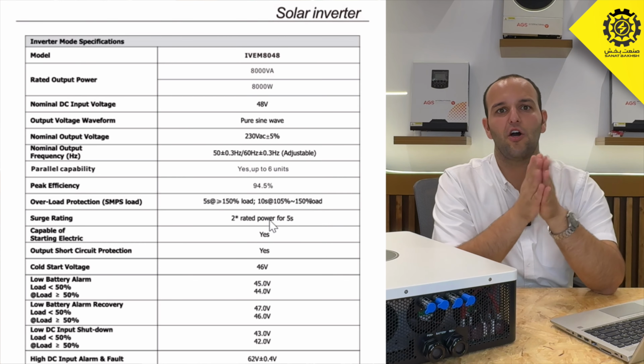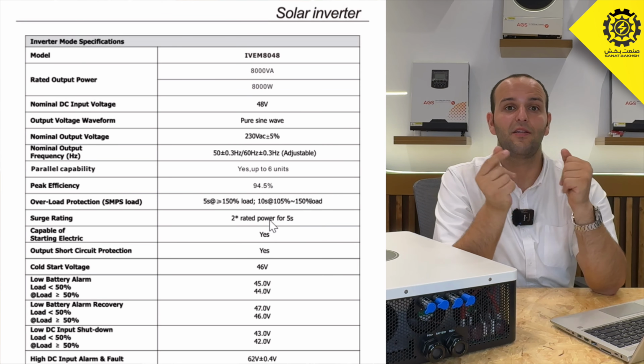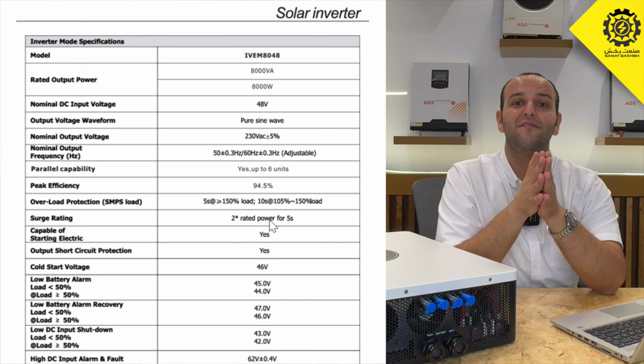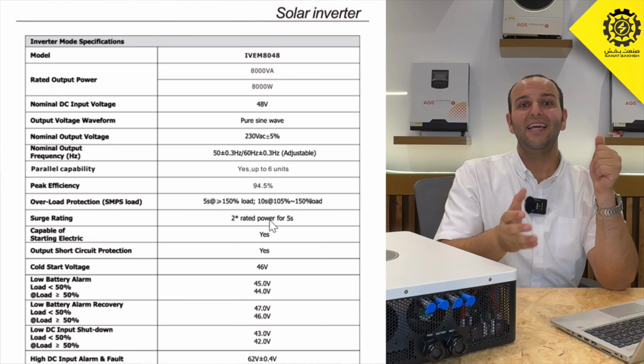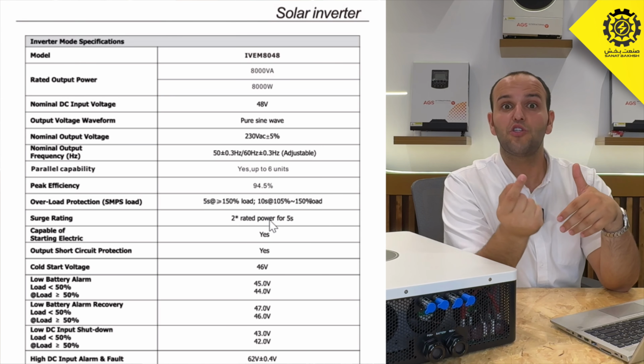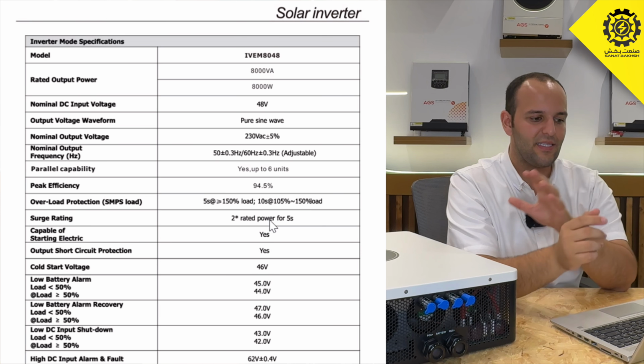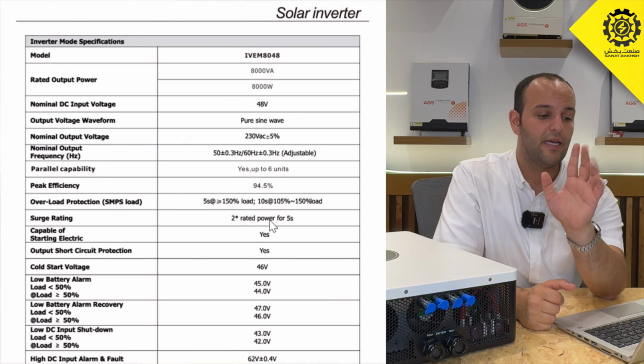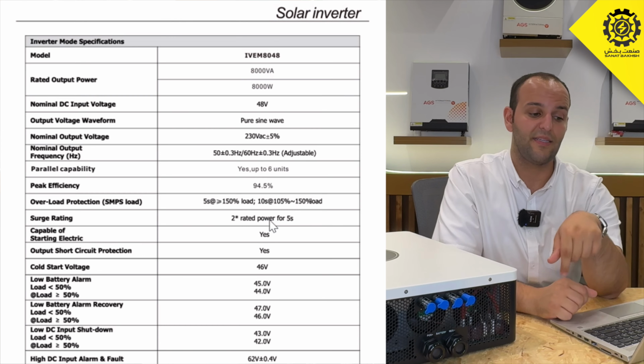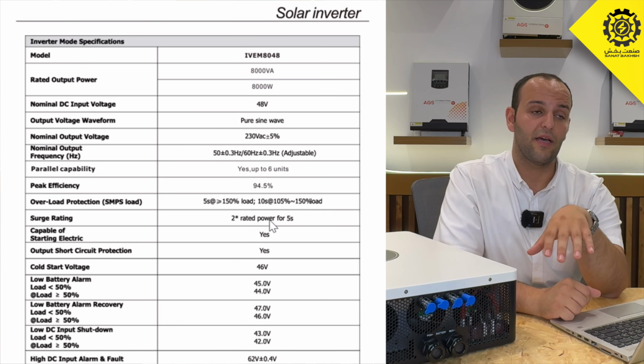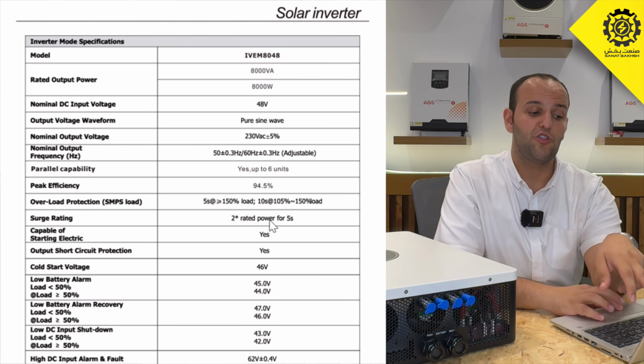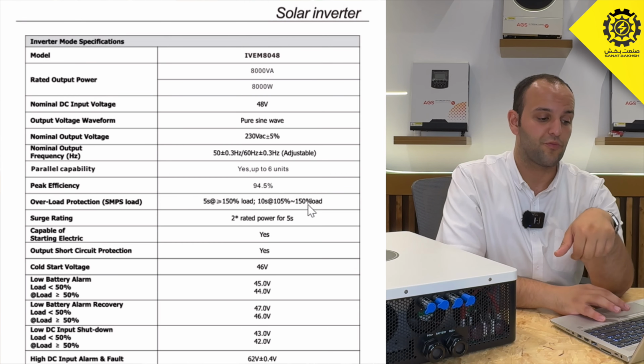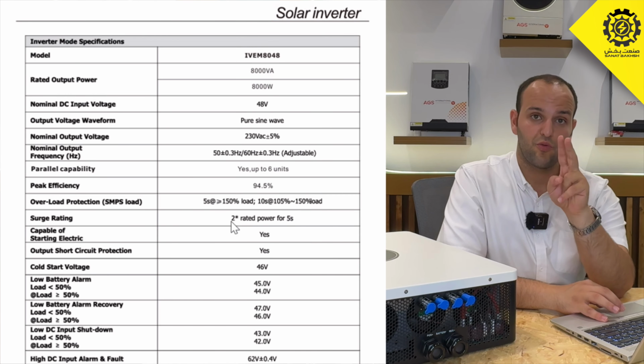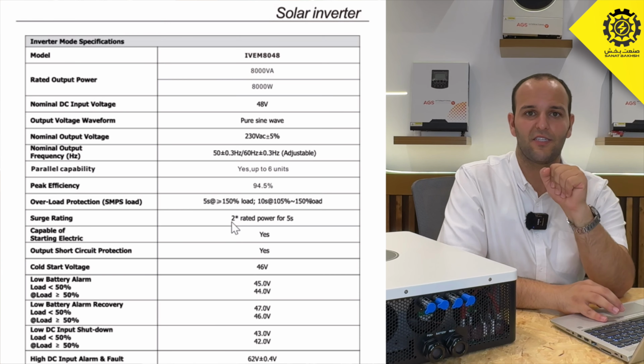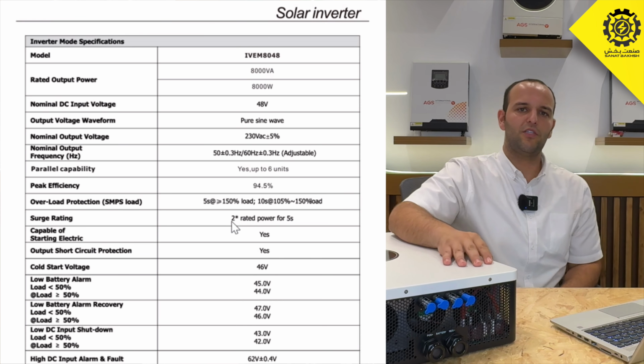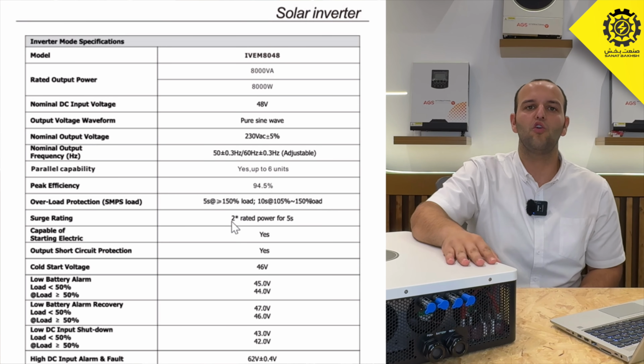For example, if you turn on your water pump, say 1 horsepower. 1 horsepower is 750 watts. At the start, it needs around 1200 watts to turn on. It means surge power. This inverter can provide for you 150% load for 5 seconds, and for 10 seconds it can provide from 105 to 150% load. Surge rating is 2 times rated power for 5 seconds. For example, this is 8 kilowatt, it can generate 16 kilowatt, but only for 5 seconds.